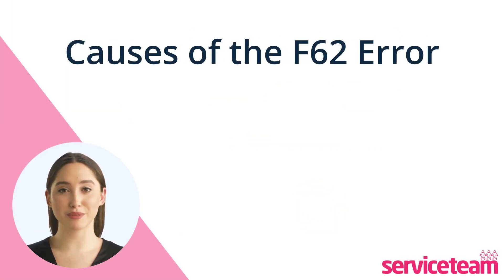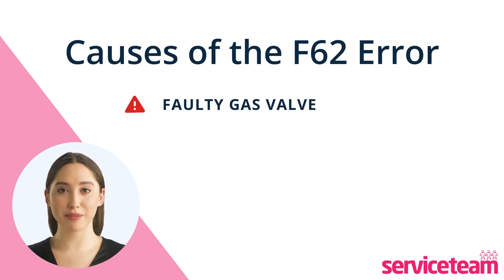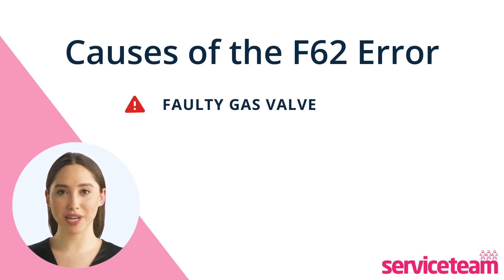Let's understand what causes the F62 error. One reason for the F62 fault code is a faulty gas valve. This valve can prevent gas from reaching the burner, resulting in the boiler malfunctioning. The gas valve's role is to control the flow of gas to ignite the burner, but if it's not opening or closing correctly, the boiler won't function properly.